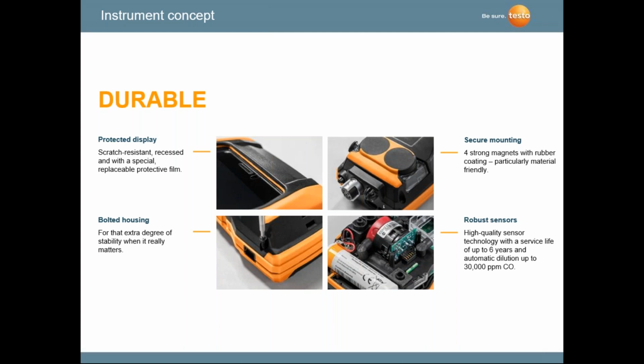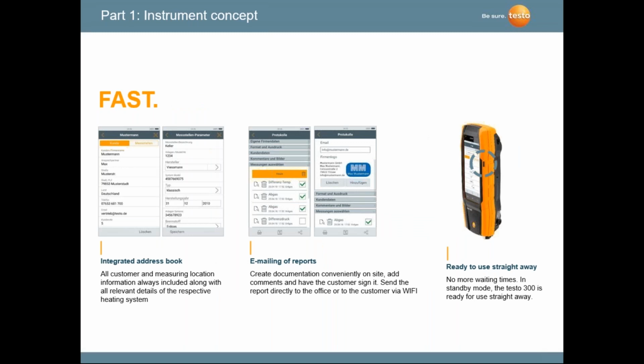Very protective lens cover, very strong housing bolted together. It has 4 magnets that hold very well on furnaces and boilers. And the sensors are digital sensors that can last up to 6 years. The 300 has the capability of 2 sensors, oxygen and carbon monoxide, and also has additional space for a third sensor, which would be the NO portion. Our standard measurements in the 300 are going to be pressure, temperature, both stack temperature and ambient air temperature or primary air temperature, oxygen, and carbon monoxide. And then we have a model that actually includes the NOx sensor, or the NO sensor, as well.